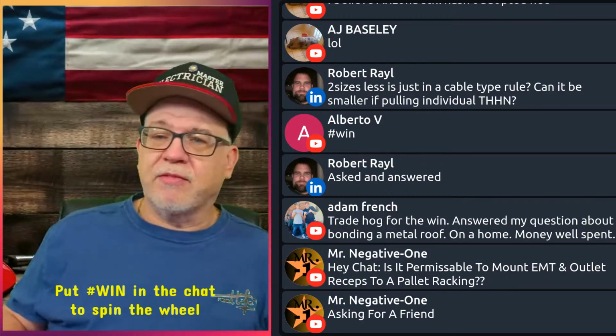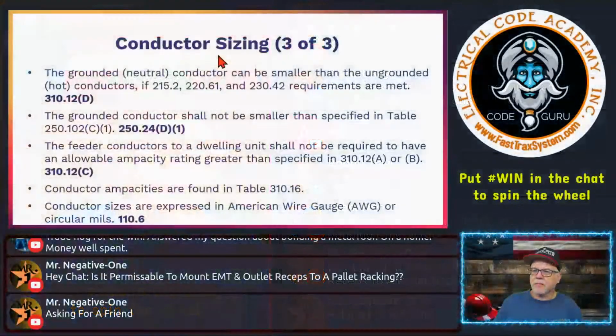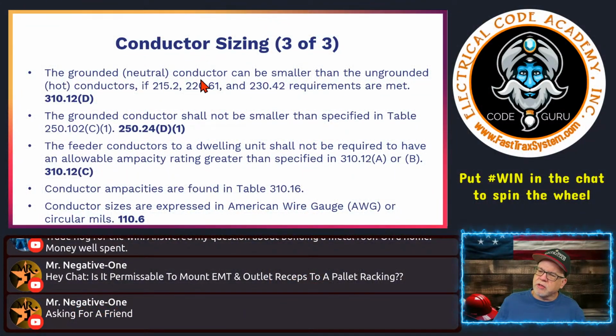Okay, so sizing of the conductors here. Let's get back to the lesson. The grounded neutral conductor can be smaller than the ungrounded hot conductors if, as we said earlier, 215.2, 220.61, you heard me call these references out earlier, and 230.42 requirements are met. Okay, so got to handle the neutral load. Have to take into consideration 230.42 if we have any continuous loads at 125% and non-continuous loads at 100%.